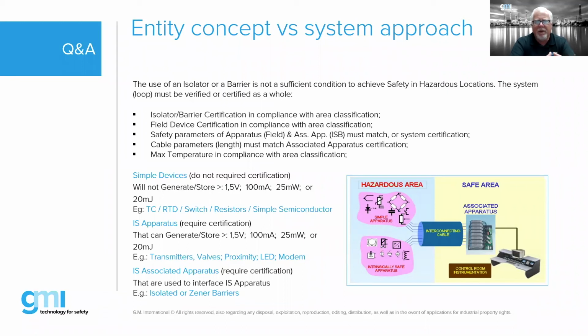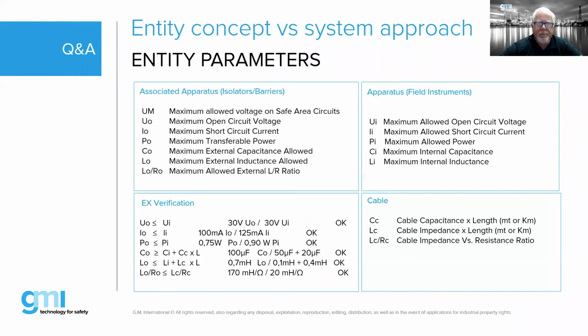Types of things that are simple devices are things like a thermocouple, a switch, a simple semiconductor, so non-energy-storing devices. However, we do require certification on IS apparatus, things like transmitters and proximity sensors. And again, the associated apparatus, which are our isolators and Zener barriers, require certification. So at the end, both devices, the associated apparatus and the apparatus, have been given full certification, a set of parameters which you need to match. That's correct. A lot of people get confused by this. It's not that difficult, but you just have to go through it and make sure that the output parameters of your associated apparatus match up with your field device.